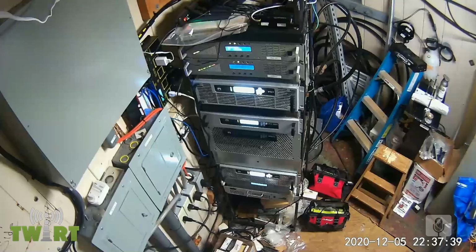So, Chris, the last technical thing to talk about: remember how with the Nautel transmitter, I needed to be able to cycle its power, not just turn it off remotely and turn it back on, because it says, I'm not coming on because I had too many power bumps. So what I did is I bought a big contactor that is normally closed. And I'm running the 240 volts from the wall to the transmitter through these normally closed contacts, so they just sit there.